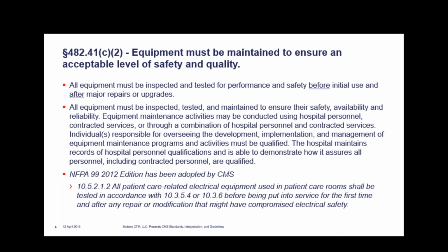The hospital maintains records of all hospital personnel qualifications and is able to demonstrate how it ensures all personnel, including contract personnel, are qualified. So, before and after, right here, a new change for CMS in 2018 is the finally adopted NFPA 99 2012 edition, which says all patient care related electrical equipment used in the patient care rooms is tested in accordance with 10.3.5.4 and 10.3.6 before being put into service and after any major repair.